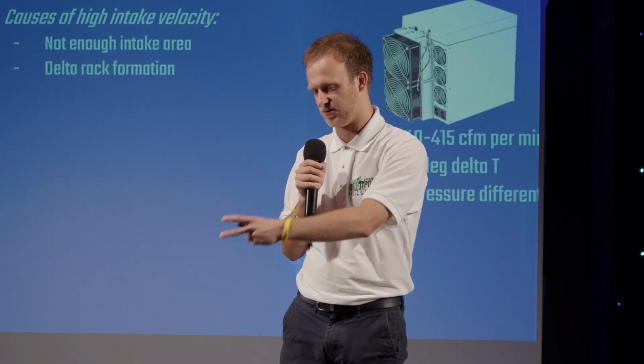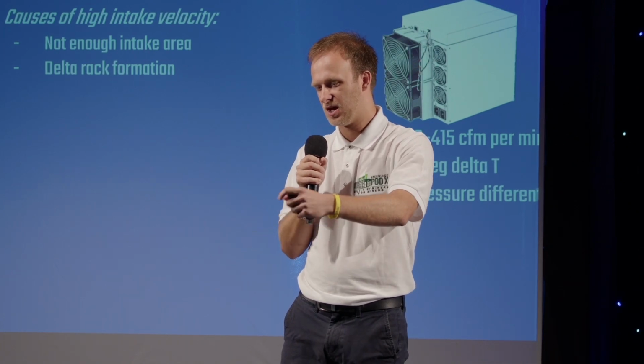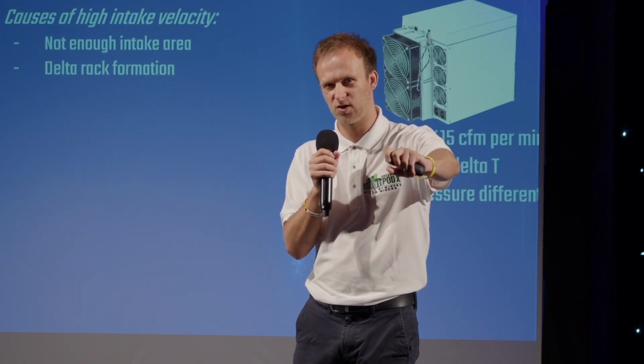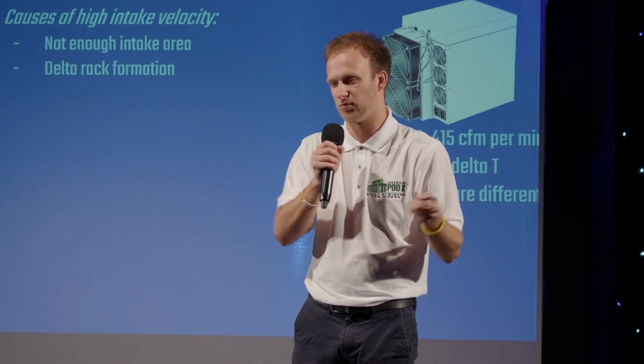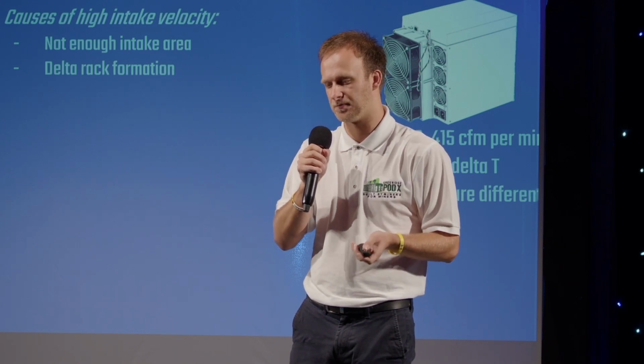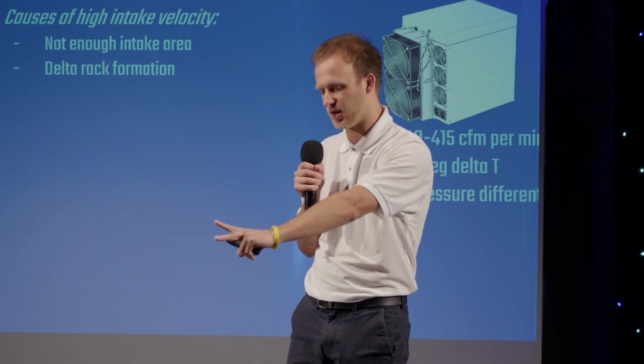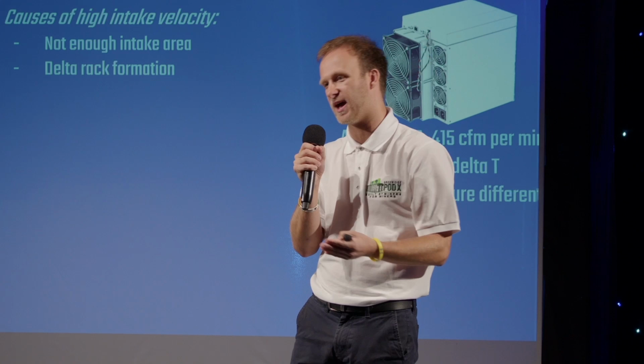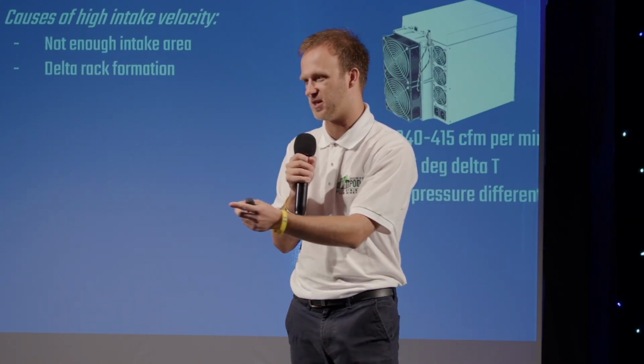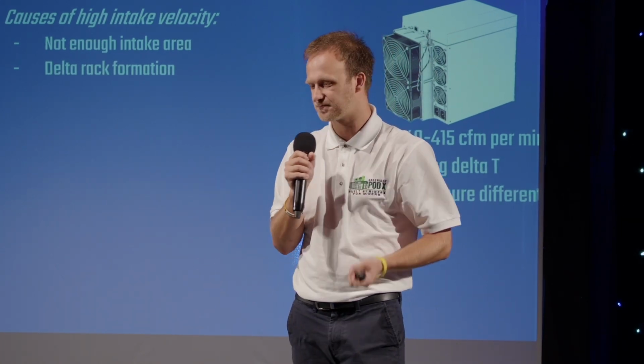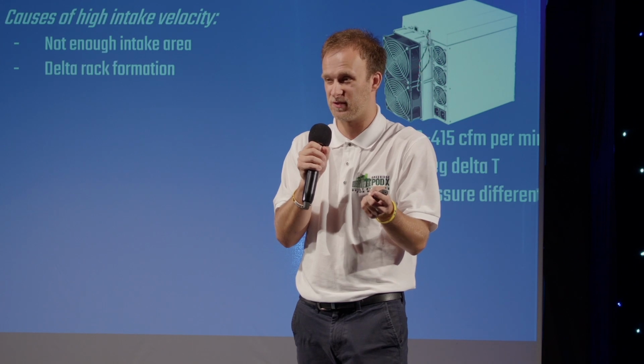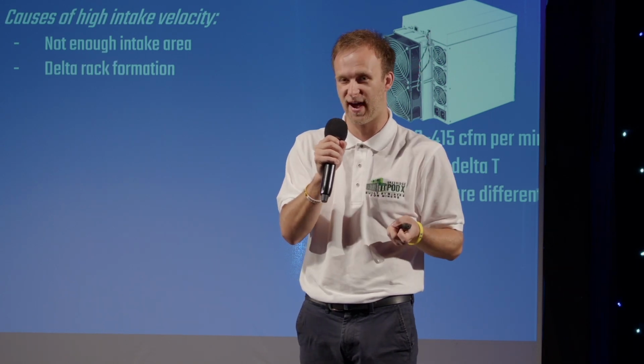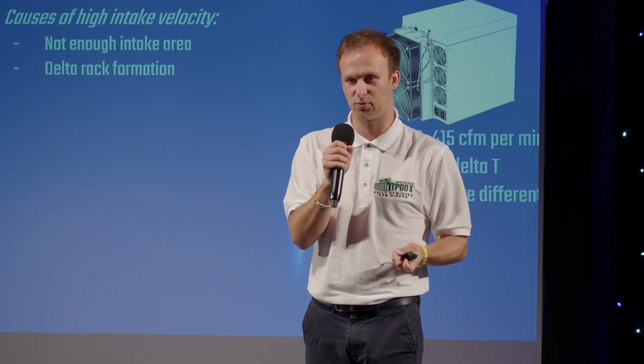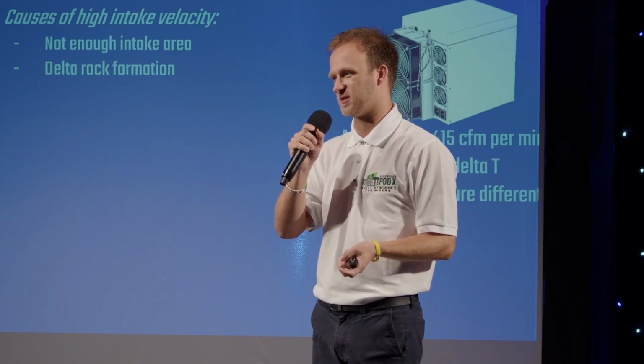That space right there is key, because you've got restrictions on your filter and your louver that speed up the air coming in regardless of what speed you're pulling at. You need sufficient area in between there to slow that air down and get it to the speed that your miner wants to pull it in at. If you don't have that sufficient area, it's going to come in way too fast. It's going to cause a lot of negative pressure in your intake, and all the problems I mentioned before are going to happen.